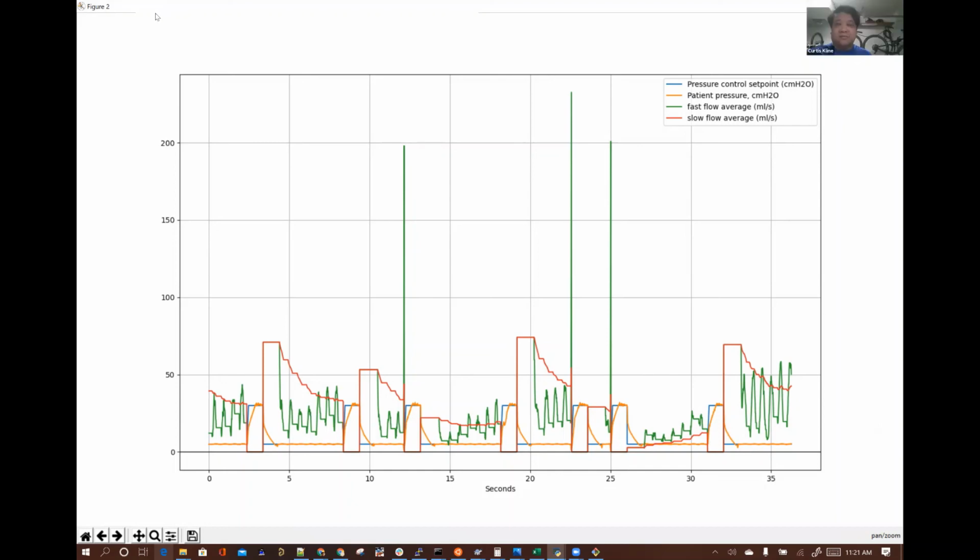That's it. Yeah, I wanted to add to that: what's also incredibly powerful about this debug tool is its test automation abilities, that we can run scripts that deliver a certain sequence of settings to the ventilator and record the data in a consistent manner. And being able to do consistent testing and collect data in a consistent manner is absolutely critical to what we're trying to do. So I too am very proud of the effort that the software team has put in to create this incredible tool.